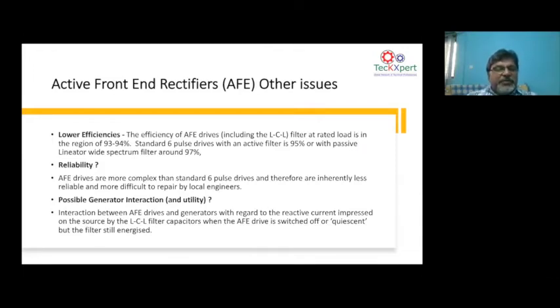Reliability is a question in active front-end drives because there is a lot of electronics. So there is the possibility of service, the cost of service, replacement of cards, and it produces electromagnetic interference. All those issues. Active front-end drives are more complex. Again, active front-end drives can sometimes cause issues with the generator because of the high frequency harmonics. A generator always has a high source impedance, so it can increase the harmonic voltage distortions, which again creates instability on the generator. Go to the next.